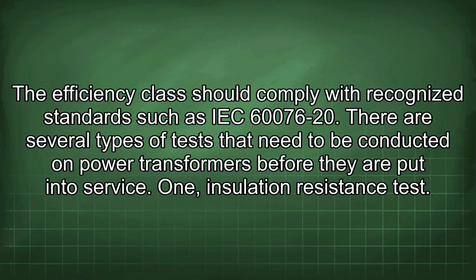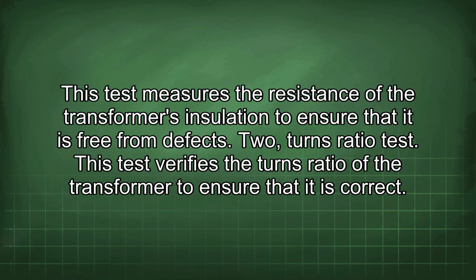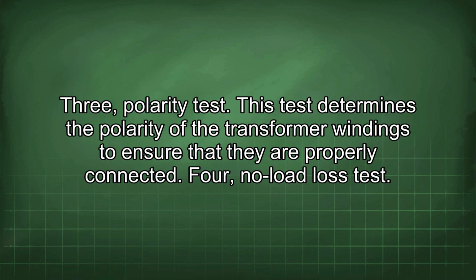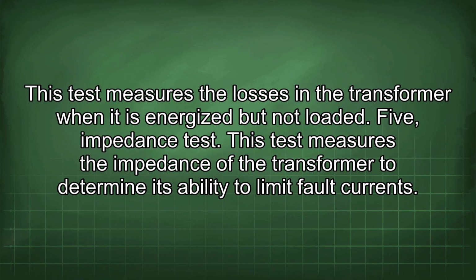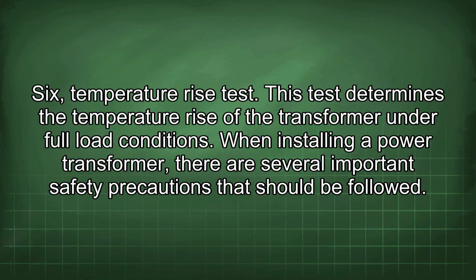There are several types of tests that need to be conducted on power transformers before they are put into service. 1. Insulation resistance test. This test measures the resistance of the transformer's insulation to ensure that it is free from defects. 2. Turns ratio test. This test verifies the turns ratio of the transformer to ensure that it is correct. 3. Polarity test. This test determines the polarity of the transformer windings to ensure that they are properly connected. 4. No load loss test. This test measures the losses in the transformer when it is energized but not loaded. 5. Impedance test. This test measures the impedance of the transformer to determine its ability to limit fault currents. 6. Temperature rise test. This test determines the temperature rise of the transformer under full load conditions.